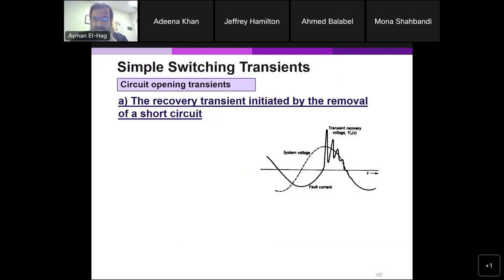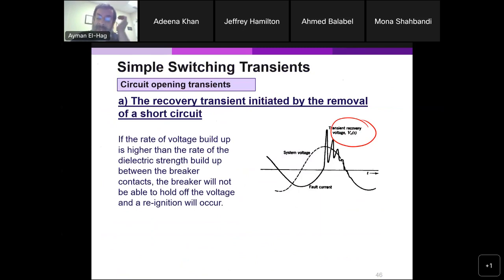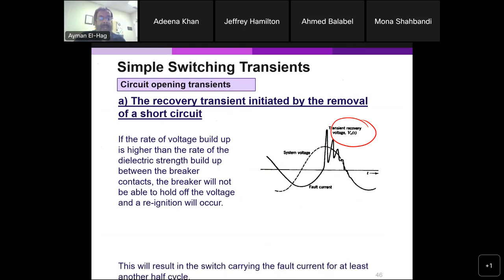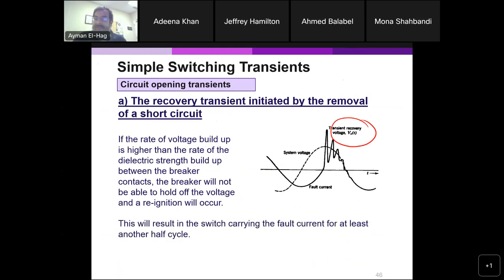So this is how the voltage looks. This is the system voltage, this is the fault current, and this is the TRV voltage across your breaker. Now, if the rate of the voltage build up, which you see here is higher than the rate of the dielectric strength build up, the breaker will not be able to hold off the voltage and there will be reignition of the fault. And you have to wait until the second half cycle, when the current goes to zero crossing, to see if it is possible for the breaker to clear the fault. So that gives you an overview of the TRV, how it is generated, and how it can impact the reignition of the fault current.